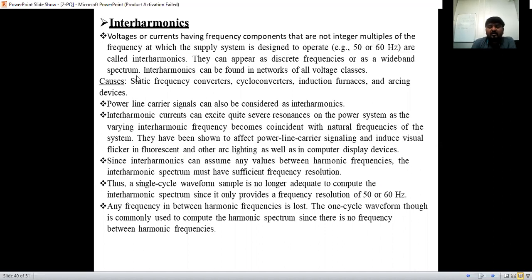So there may be voltage or current interharmonics. In the first unit we discussed this same definition, the causes being static frequency converters, cycloconverters, induction furnaces, arcing devices, arc furnaces and such. If it's not integer multiples, that is called interharmonics; if it's multiple of integer numbers, that is called normal harmonics.